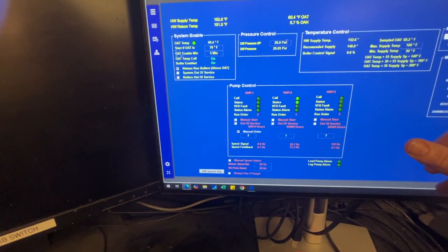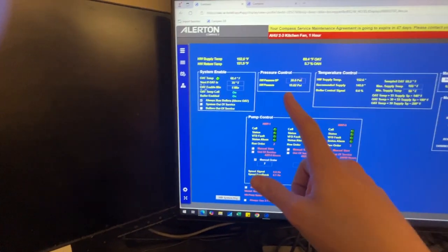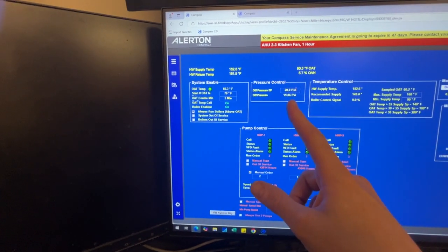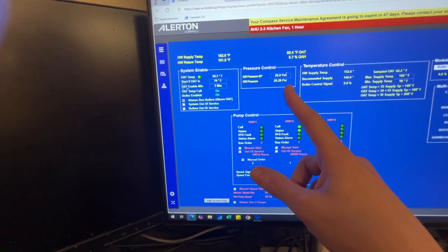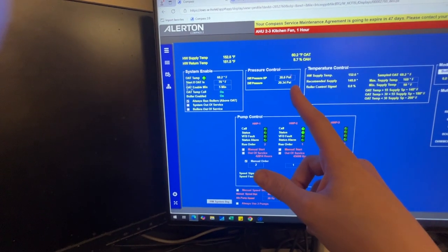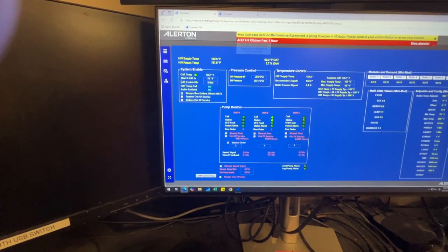Let's see. We also, our differential set point controller up there was working good. We did replace the one on the chiller loop. That one was not working properly, but just keep an eye on that. All your energy savings will go out the window if that fails. They're either going to ramp all the way up or down. You won't know what's happening.